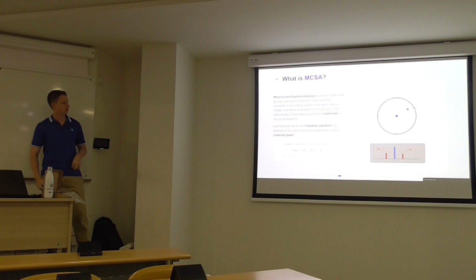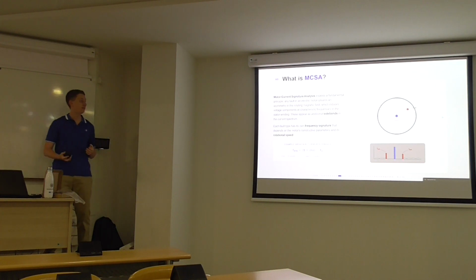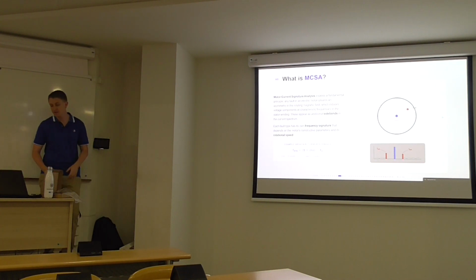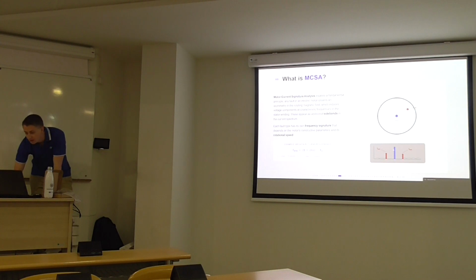So let's see an example. Let's say we have an induction motor with a broken bar. Then we measure a current, we apply the FFT, and what we will see is something like this. The highest peak in the spectrum will be the fundamental component, and next to it, two sidebands will appear. One is when we take the negative sign here, the other when we take the positive sign. So those are the signatures of the fault.